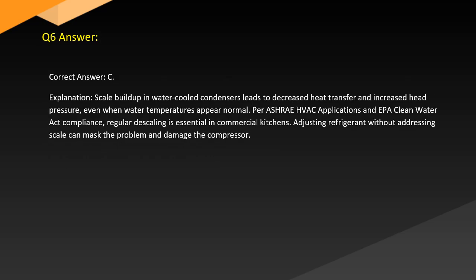Answer. Correct answer: C. Explanation. Scale buildup in water-cooled condensers leads to decreased heat transfer and increased head pressure even when water temperatures appear normal. Per ASHRAE HVAC applications and EPA Clean Water Act compliance, regular descaling is essential in commercial kitchens. Adjusting refrigerant without addressing scale can mask the problem and damage the compressor.